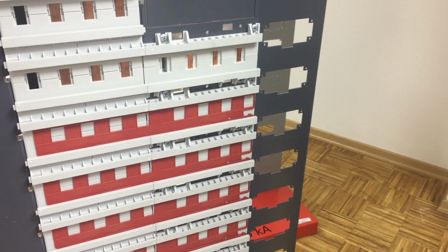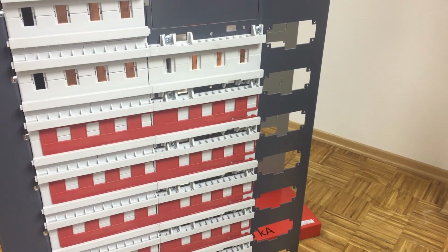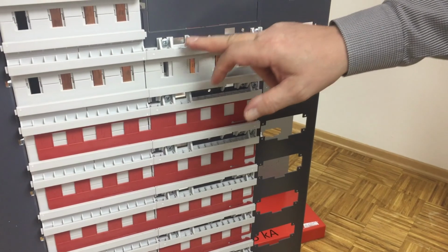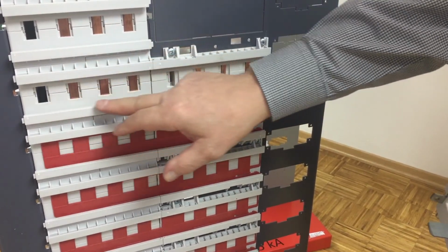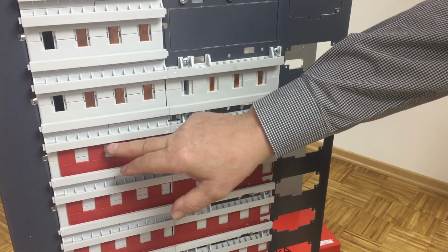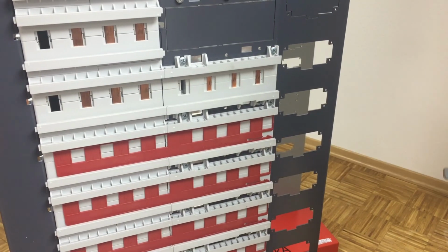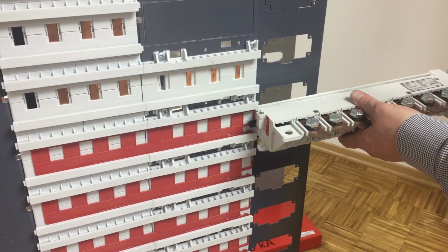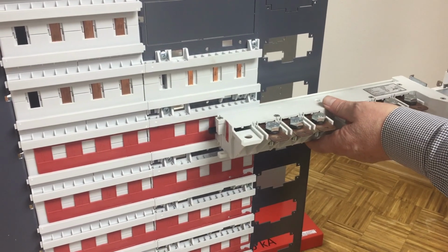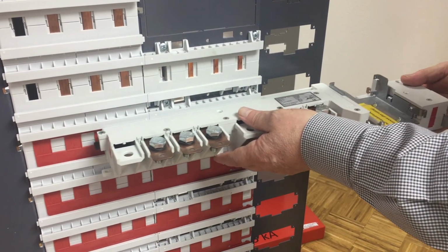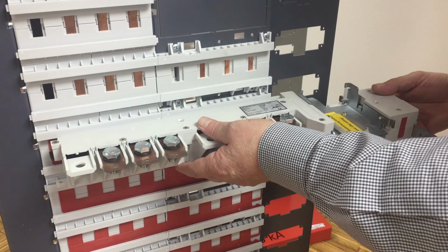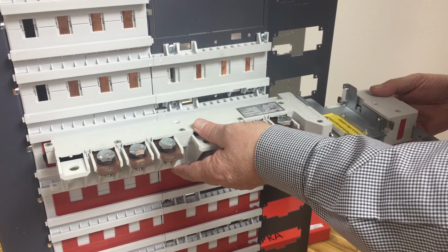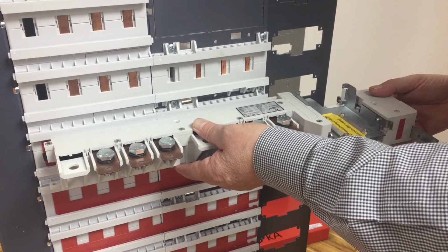So how do the units work together? Cable module, as we see it here, busbar module, together with a combined shutter system and a contacting module. You can insert it as demonstrated here. Together, these three parts form up a completed closed system.